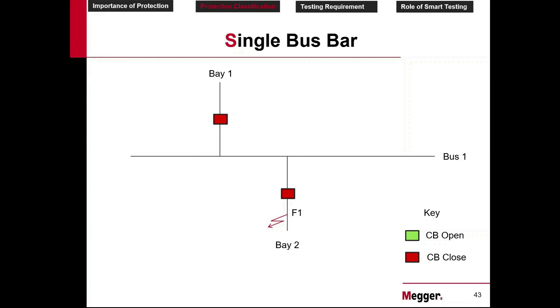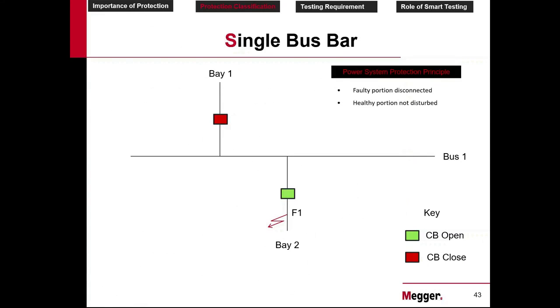So should we open this breaker, bay 1 breaker, or should we open bay 2 breaker? By looking at it, we say that it should open bay 2 breaker. But now we want to know why we are saying that. What is the reason for choosing this breaker and why not this breaker? The answer lies in the principle that we discussed. Whichever breaker we choose should be based on this principle.